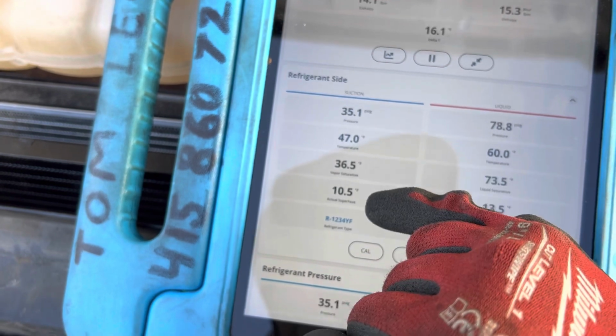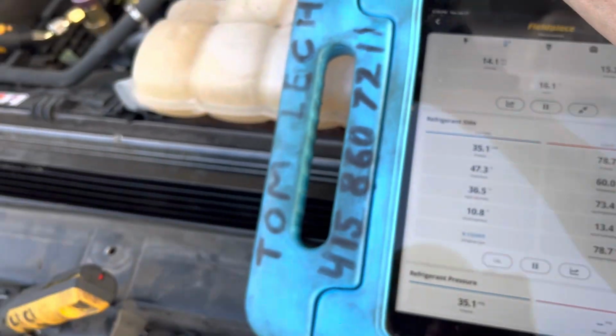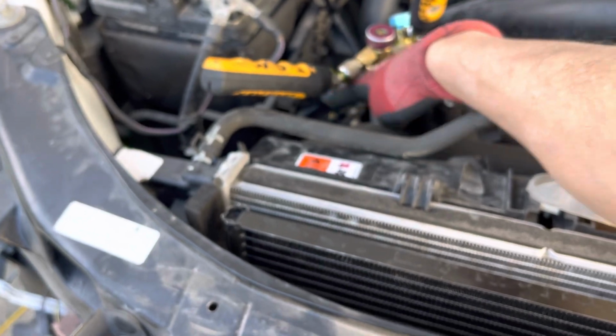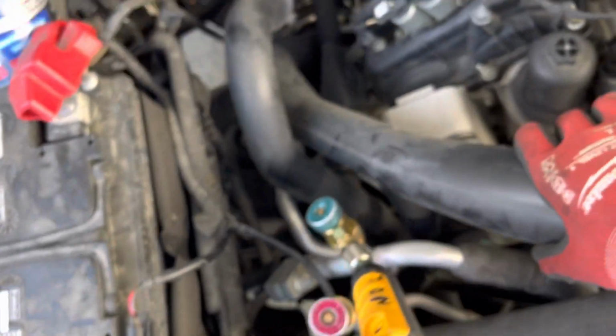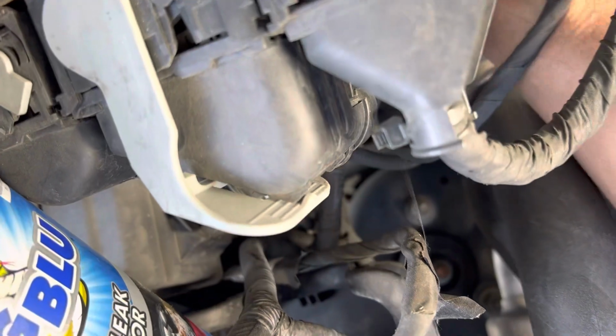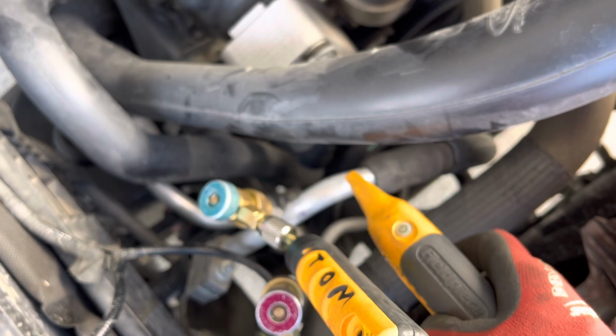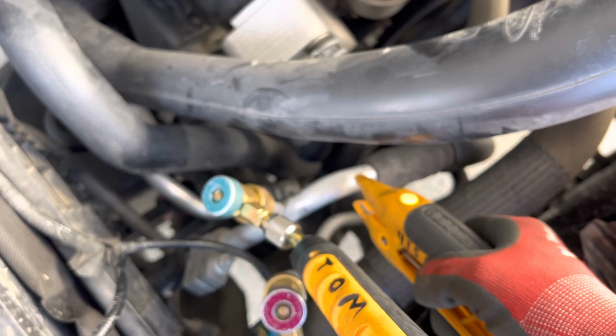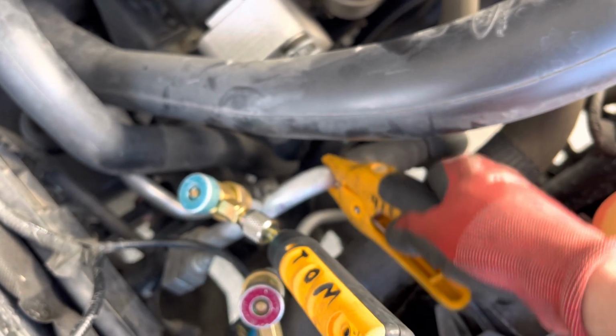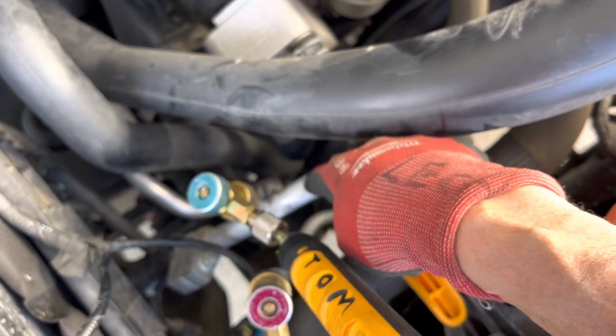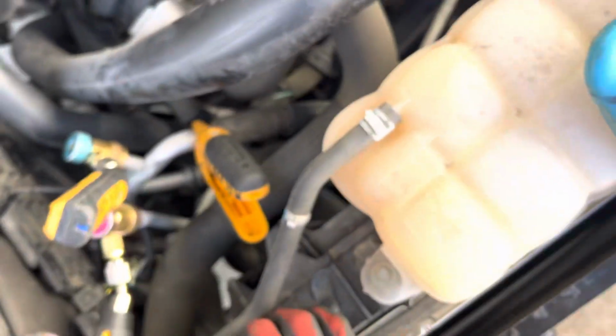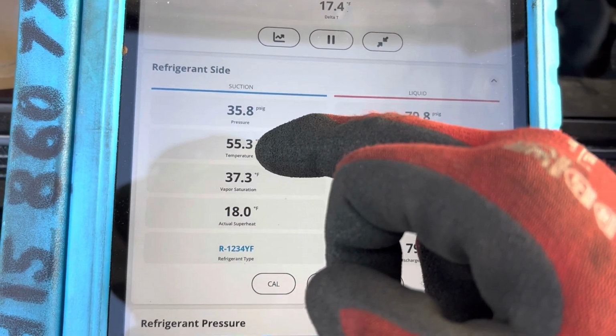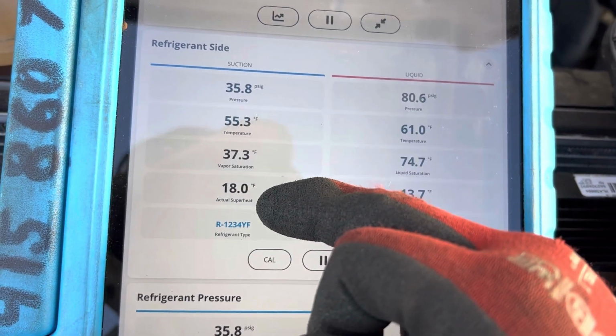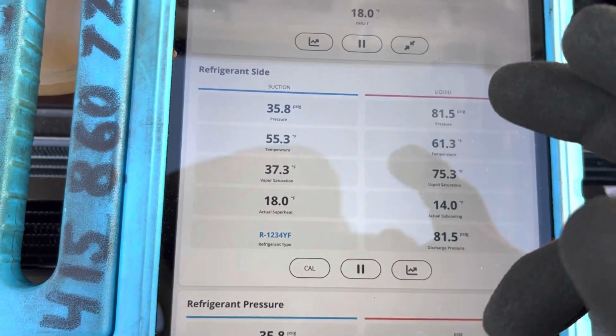Now watch what happens when I move it. I'm gonna go grab that sensor and I'm gonna move it right here. This is after the internal heat exchanger. You're gonna see the temperature change. This is the temperature going back to the compressor. So, and it can't be painted. It has to be bright, shiny metal. So there I go. Now I'm attached at this point. This is after the internal heat exchanger. Now the temperature is 55 degrees and our superheat's 18.